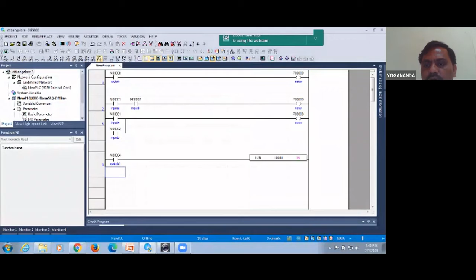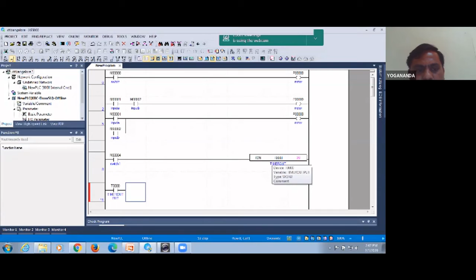As I explained in the previous ladder diagram, power always flows from left to right. This timer output, we need to consider in one of the switches. That is called the timer output switch. So T0 timer output, I'm going to give timer output. You can see now this switch is exactly the status of the timer. When M4 is on, the timer is going to generate its delay, and after the generation of delay, the switch is going to produce that particular output.